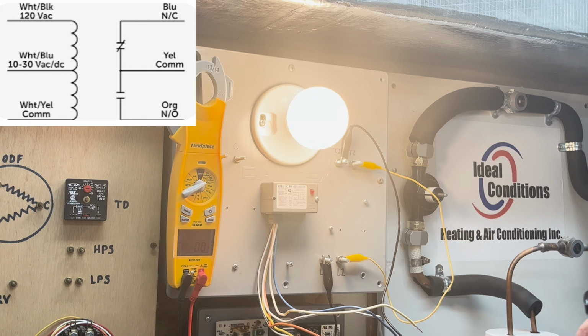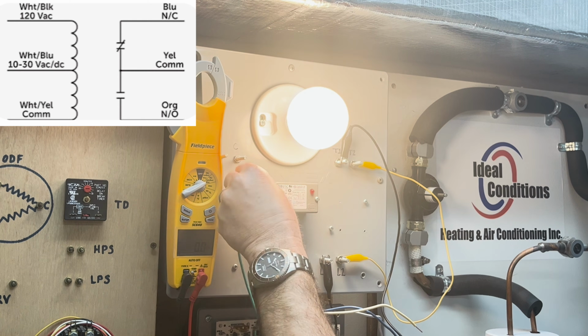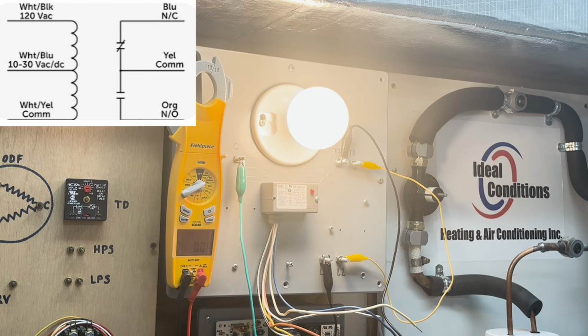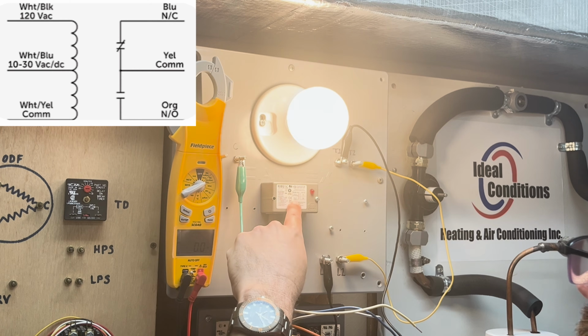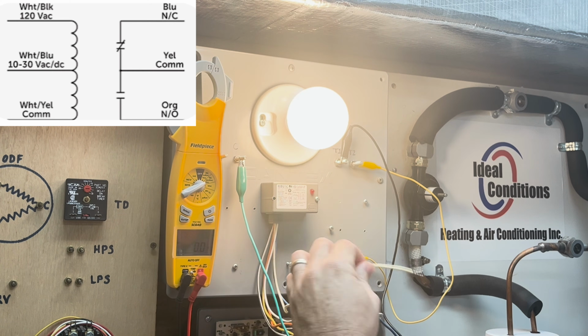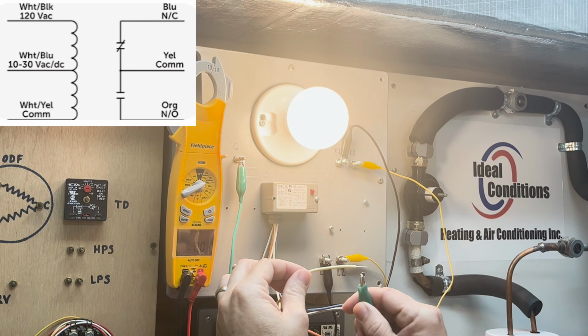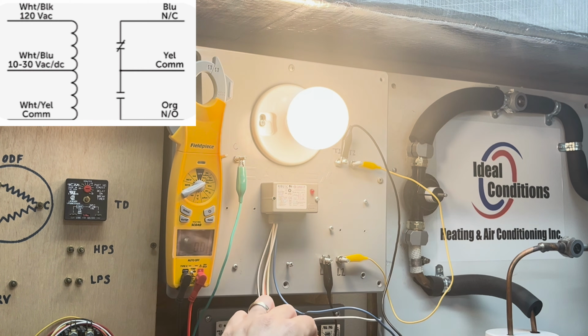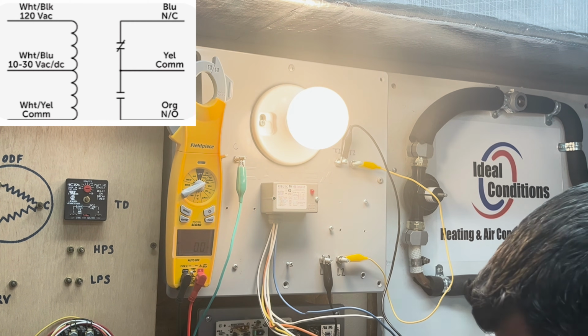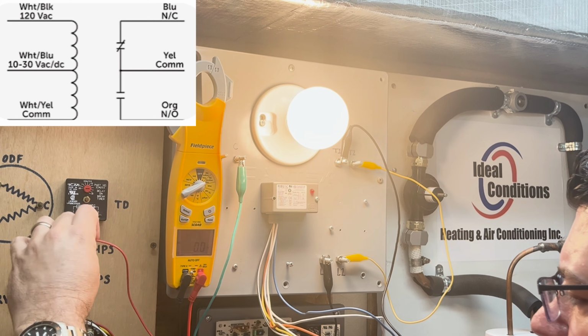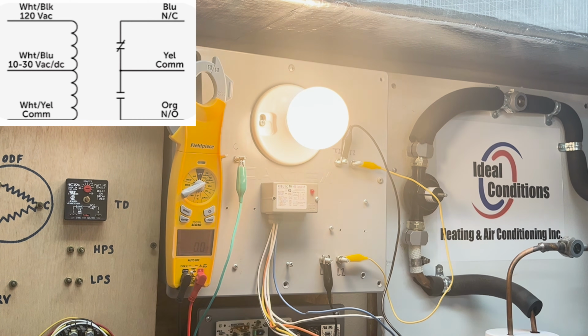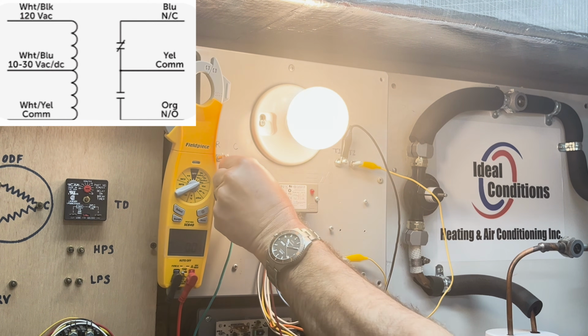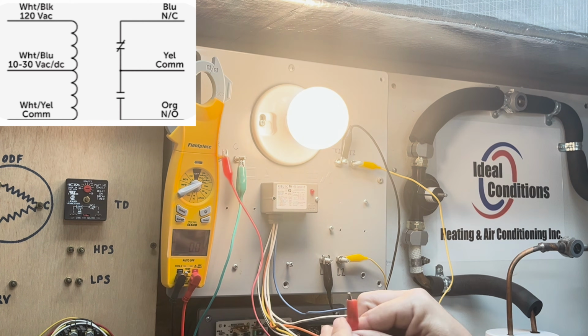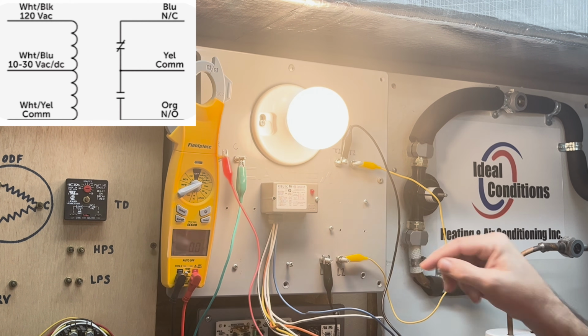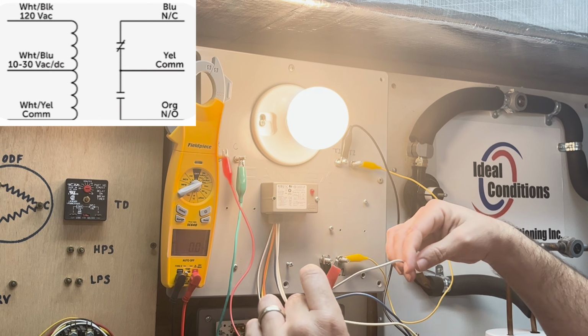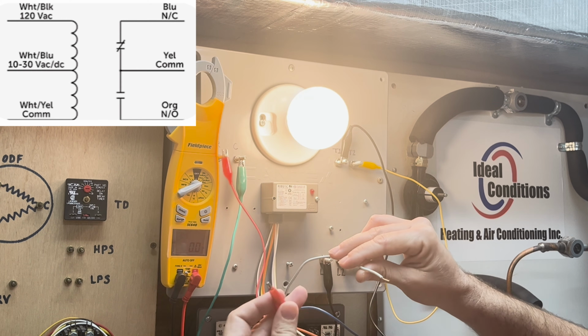I'm going to use green for common, and it says here, common would be white/yellow. Well, that's white/yellow, so I'm going to go ahead and connect to here. Then I'm going to take another wire. We'll just use this red one here, and we'll use this as our 24 volts alternating current. That's going to go to white/blue. Okay, so this is our white/blue, and the moment I connect this, we'll have 24 volts.